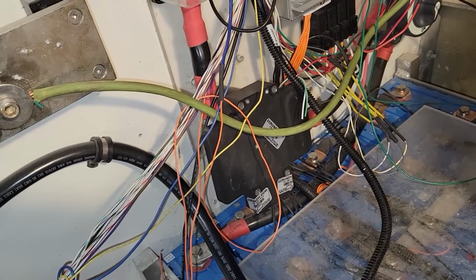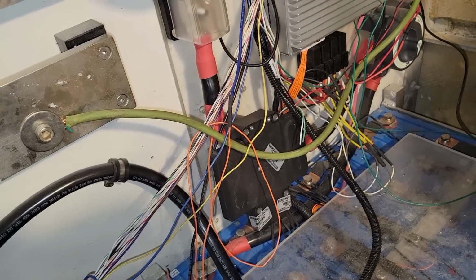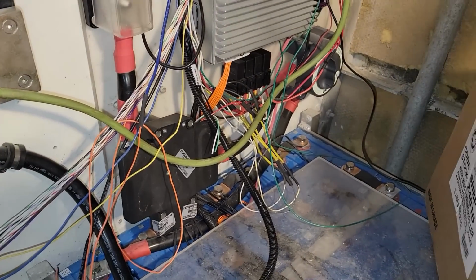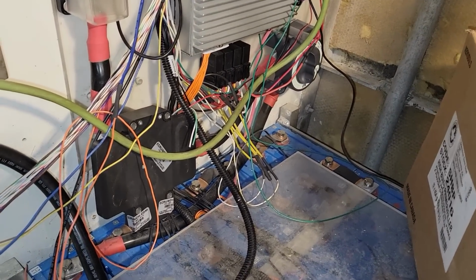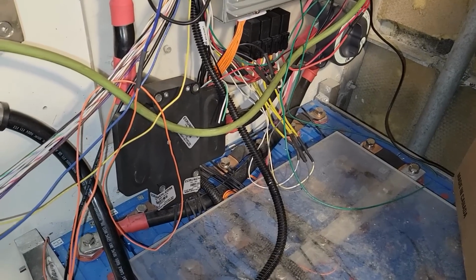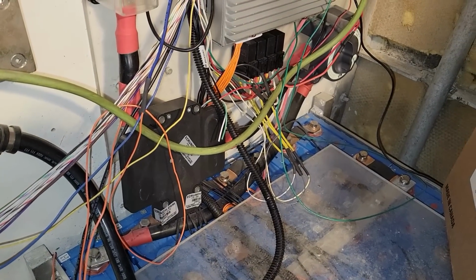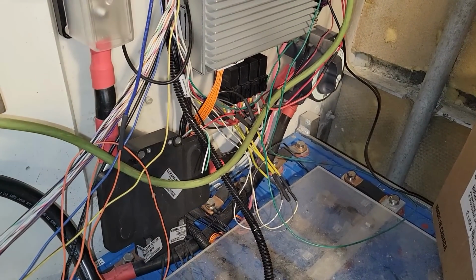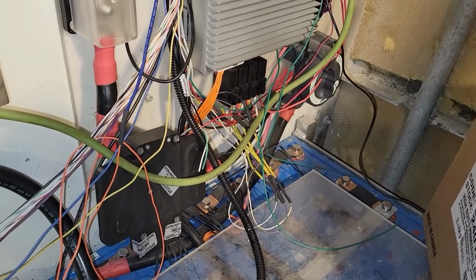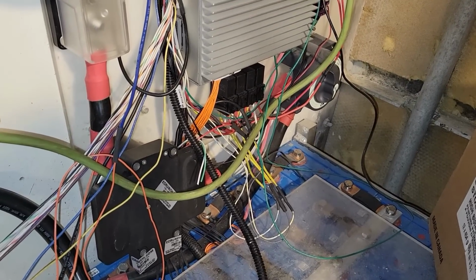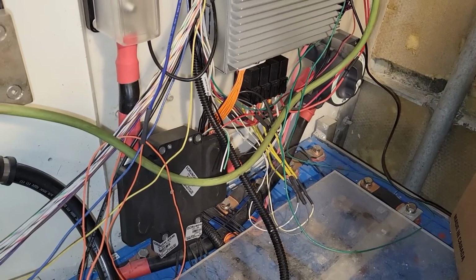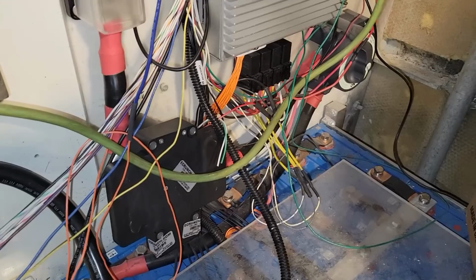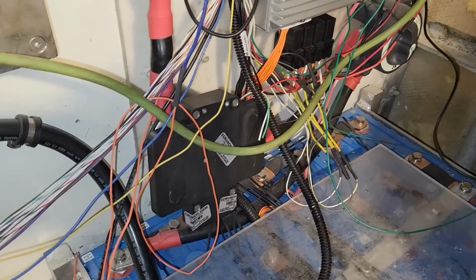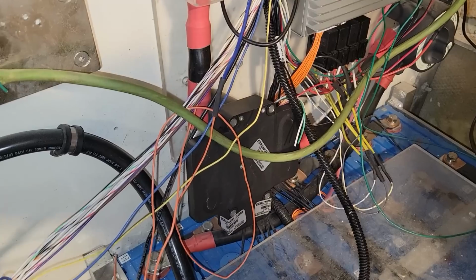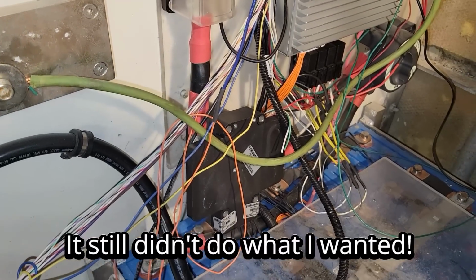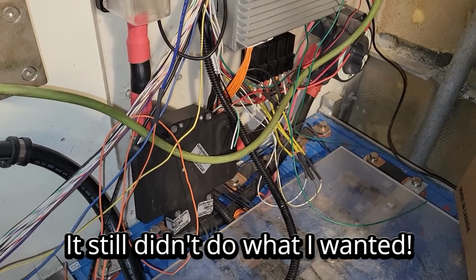Just after doing the cables alone, without the actual contactor change, I went from 200 amps to 330 on initial startup, but then it dropped again from 330 down to 260. So the only hot part on the whole system were the contactors. Hopefully this will get those working a bit better. We'll find out here, I'm just going to run it up now and find out.